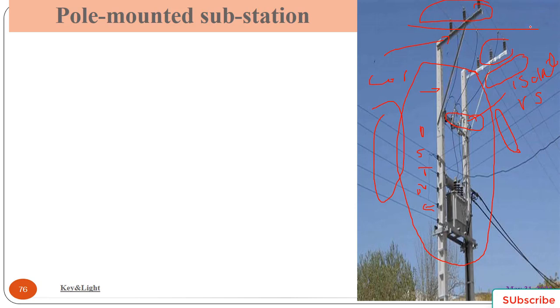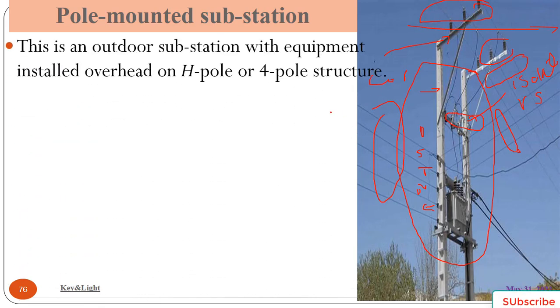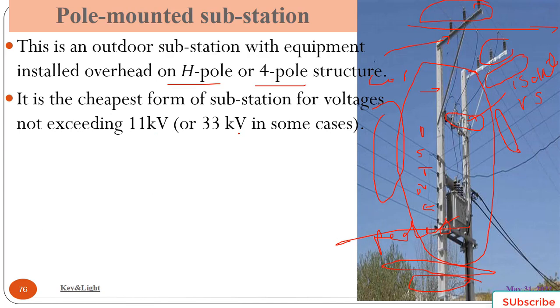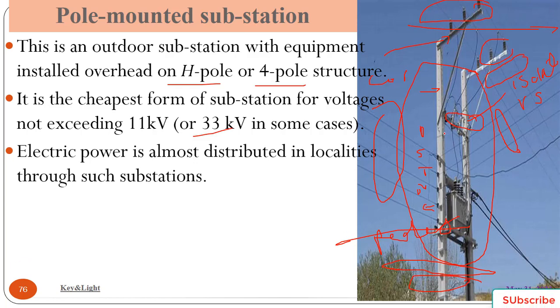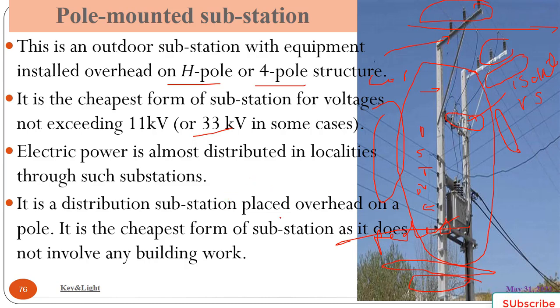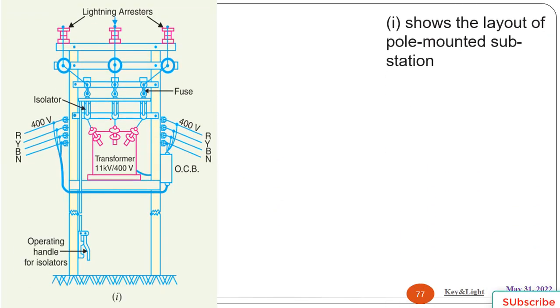It's also the other which passes in this direction. So this is an outdoor substation with equipment installed overhead on an H pole or four pole. See, in this case, this is an H pole. These two are poles. It is the cheapest form of substation for voltage not exceeding 11 kV, or 33 kV in some cases. In our city, 15 kV is distributed over the distribution line. Electric power is mostly distributed in localities through such substations. It is a distribution substation placed overhead on a pole. It is the cheapest form of substation as it does not involve any building work.